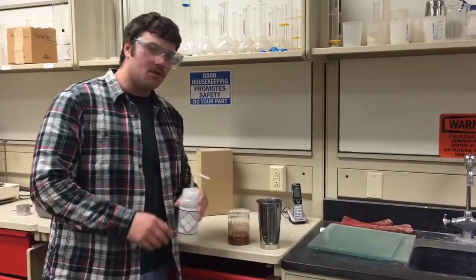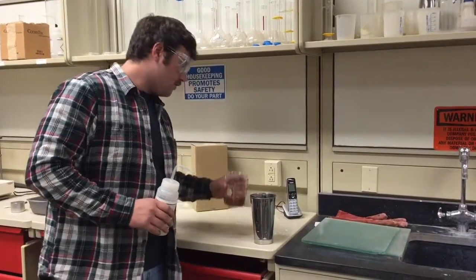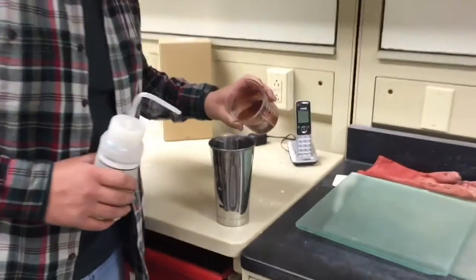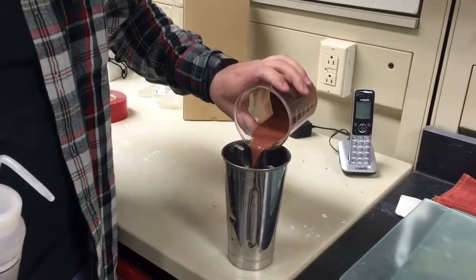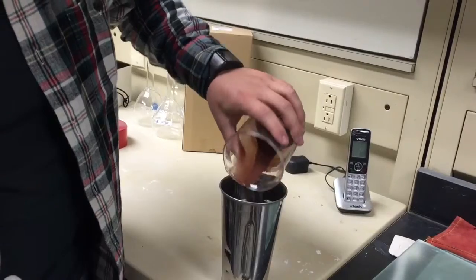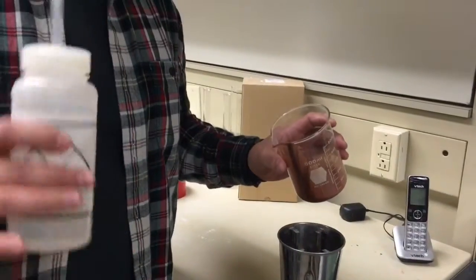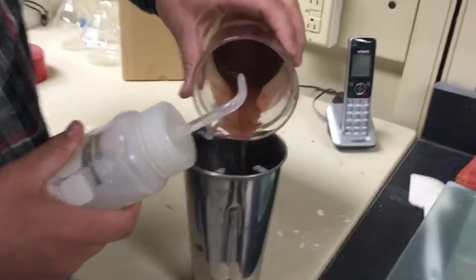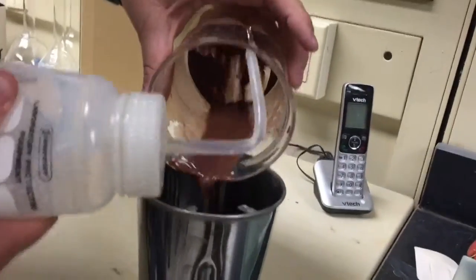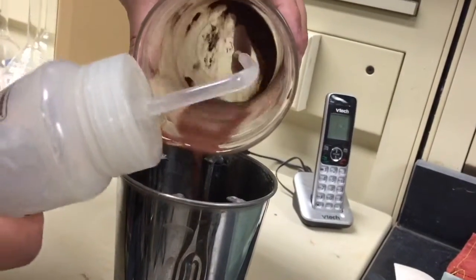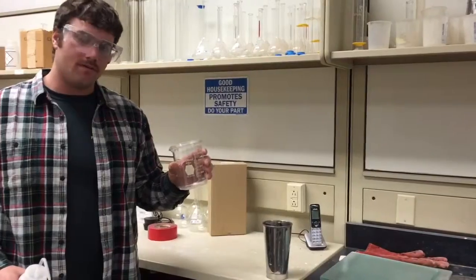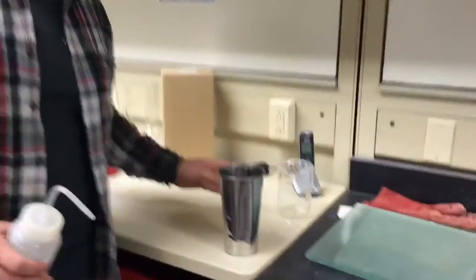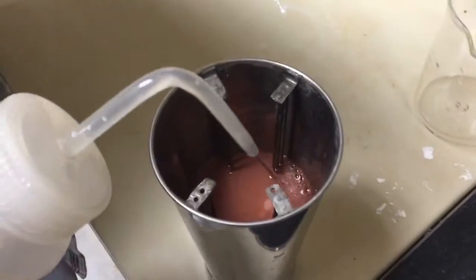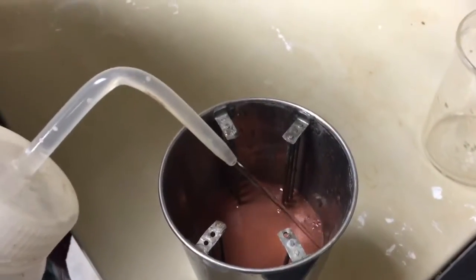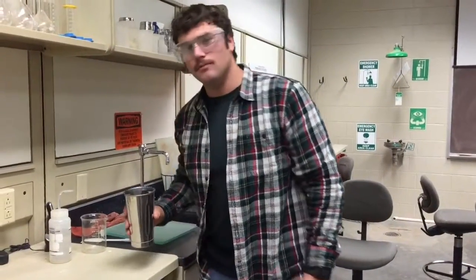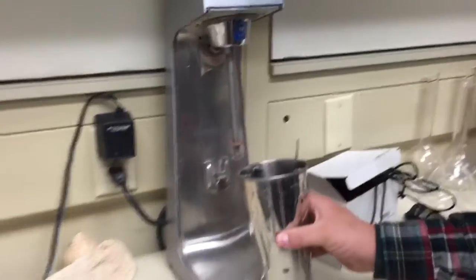After letting our specimen soak for 5 minutes, we're going to transfer from our beaker into the mechanical dispersion cup, being careful not to lose any part of our sample. The remaining needs to be washed out with distilled water, so we get everything into the dispersion cup. After transferring all of our specimen into the dispersion cup, we're going to make sure that the volume is about half full. The amount of water that you add does not matter. After adding your water, you're going to get it mechanically dispersed for 1 minute.